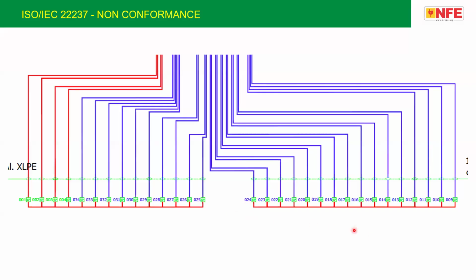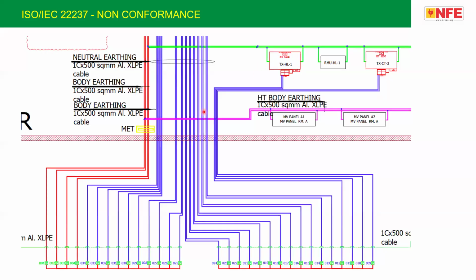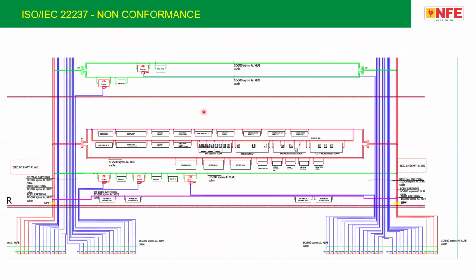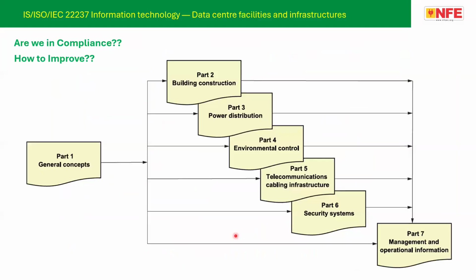Now, if you look at each of these, it goes to some parts of the building, like 1, 2 go to the body of transformer number 1, another 2 go to the body of transformer number 2. If you look at the entire building, there are so many earth electrodes installed, which is a very clear violation of the standard, either TIA or ISO or whatever.